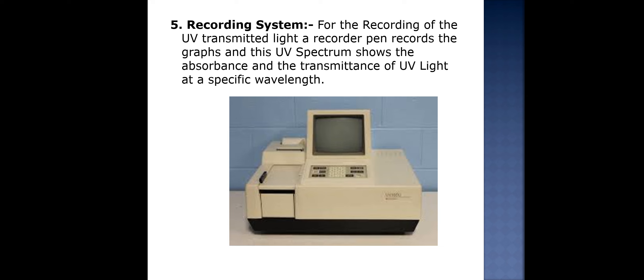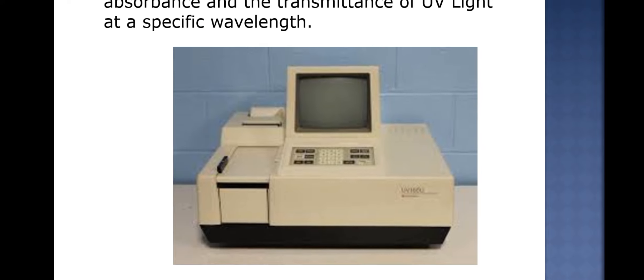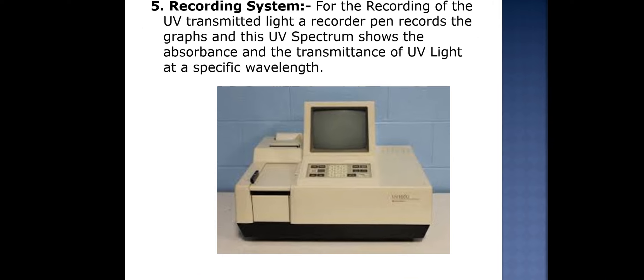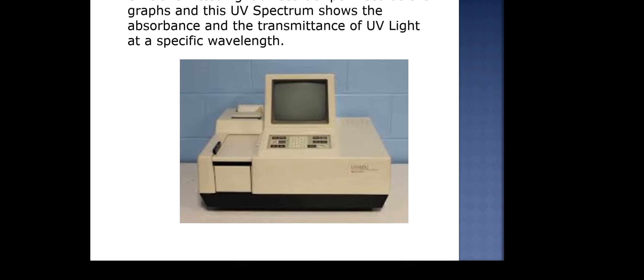The fifth instrument is the recording system. For recording UV transmitted light, a recorder pen records the graphs, and the UV spectrum shows the absorbance and transmittance of UV light at specific wavelengths. This is the general UV visible spectrophotometer, which is automatically connected to a computer. The model shown in the image has its own screen and displays the graph by itself.